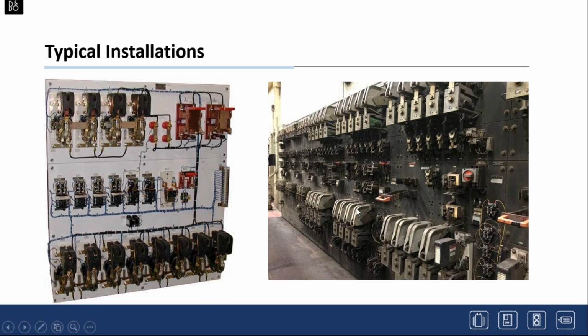These are the old IC2800 contactors with the very large arc chute that expends the arc out into the atmosphere. In the lower corner here is a DS303 replacement, and here's another one of those IC2800 contactors. So you can see how the footprint of the DS303 is generally smaller than the related IC2800 device. Again, this is a dead front.